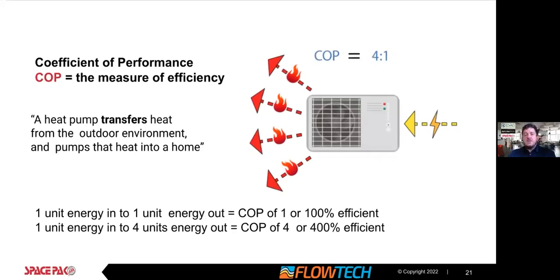So let's talk a little on COP as a measure of efficiency of heat pumps. As mentioned, a heat pump transfers heat from the outdoor environment and pumps it into the home. It's not creating heat by burning anything, obviously, and it's gathering that free energy that's outside. On the graph, 1 unit in and 4 units out is a COP of 4. 1 unit of energy in to 1 unit of energy out is a COP of 1, or 100% efficient, similar to an electric resistance heater. 1 unit of energy in to 4 units of energy out is a COP of 4, or 400% efficient, pretty phenomenal. Our units are inverter, and we'll get into COP, but the inverter capability of our units allows for some high COPs.